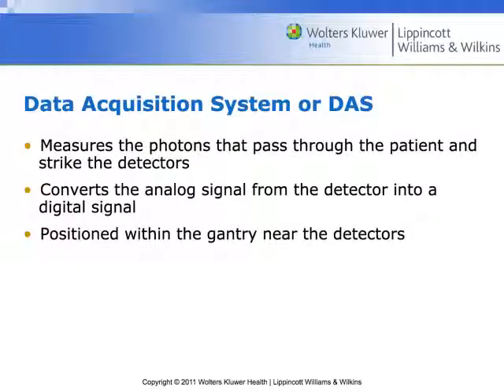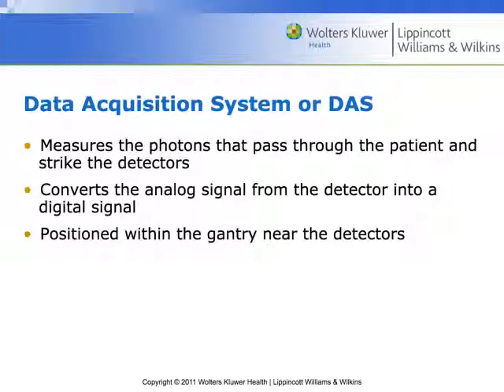The data acquisition system, or DAS, measures the photons that pass through the patient and strike the detectors. It converts the analog fluorescent signal from the detectors to a binary digital signal. It's located within the gantry, floating right beside the detector array, so the analog signal is immediately converted to a digital signal.